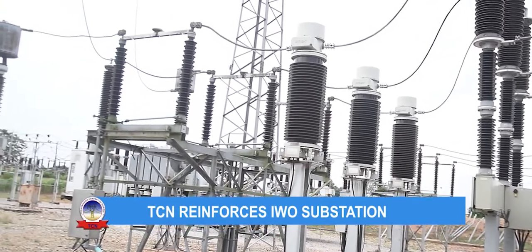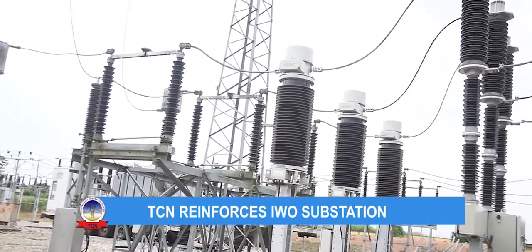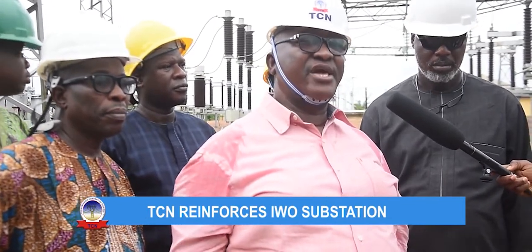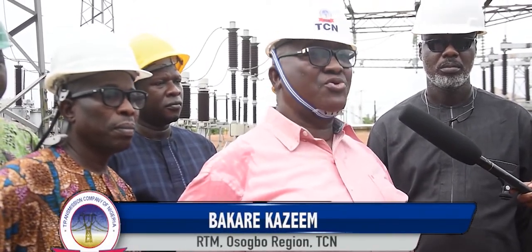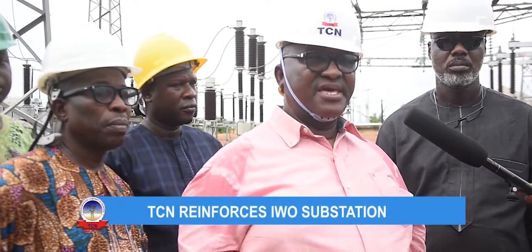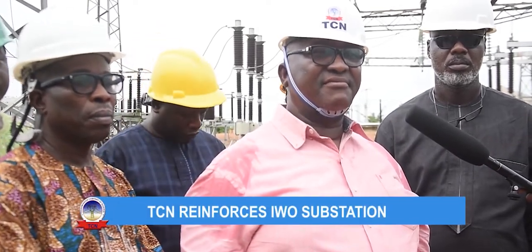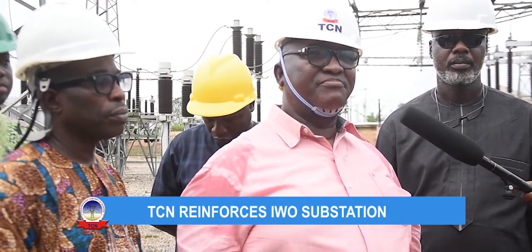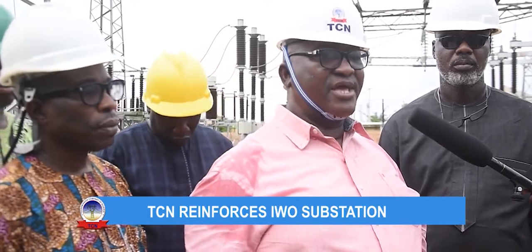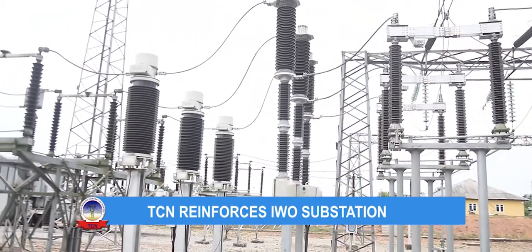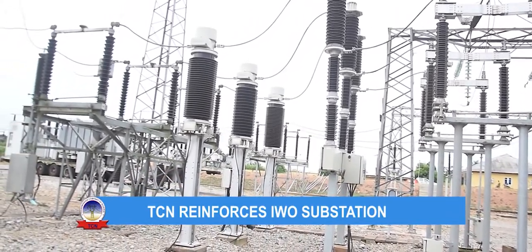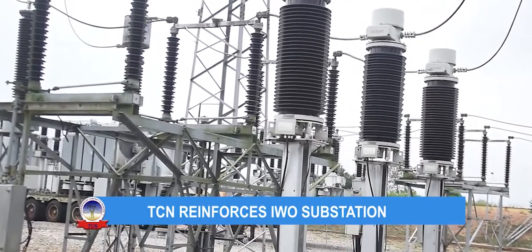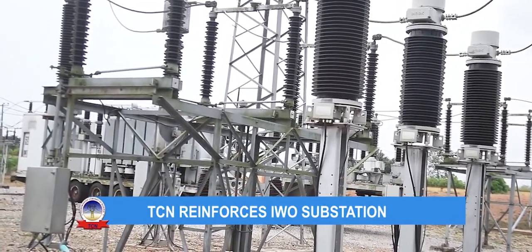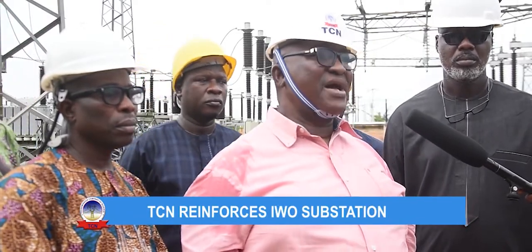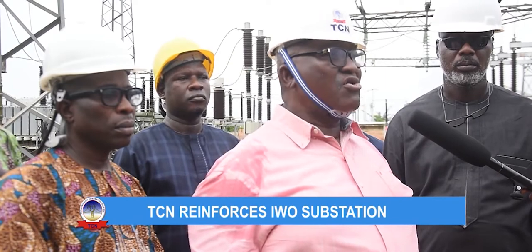Recently, we have been having a lot of problems, particularly protection problems. When there is a fault in far away Iseyin, it will upset our system either at Osogbo or at Ibadan North. In this station there are 3 infeeds: one from Ibadan North, one from Osogbo, and one going to Iseyin. All of them emanate from the 132 kV bus bar here. Before now, there were no circuit breakers and no protection, so faults here would go as far as either Ibadan North or Osogbo.